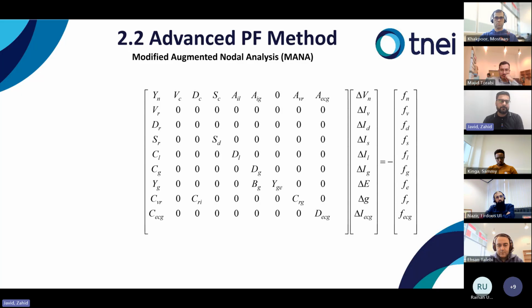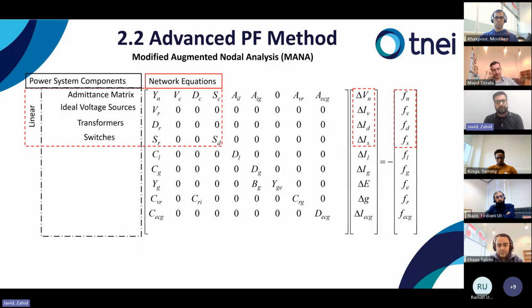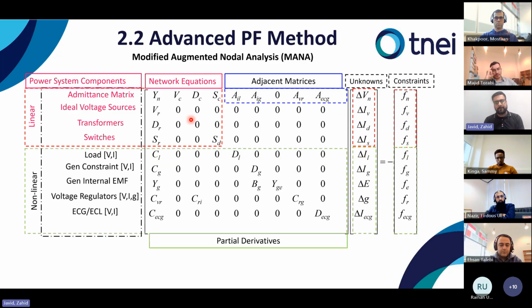Basically that is also a nodal analysis based method, but it is a modified augmented nodal analysis. Augmented means that it has augmented rows and columns that can be used to model components which are hard to model in the nodal analysis based method. If I divide this matrix into different parts, we can see that all of these are linear components. We can model all the impedances of the network in the Y bus, and then all the ideal voltage sources, transformers, and switches. So these are all linear components, which is the linear part of the matrix. In the analysis, I will show later how it helps to automate the process while using steady state analysis as well. And below are the nonlinear devices or components in the network, like PQ loads, PQ generation, and voltage regulators.